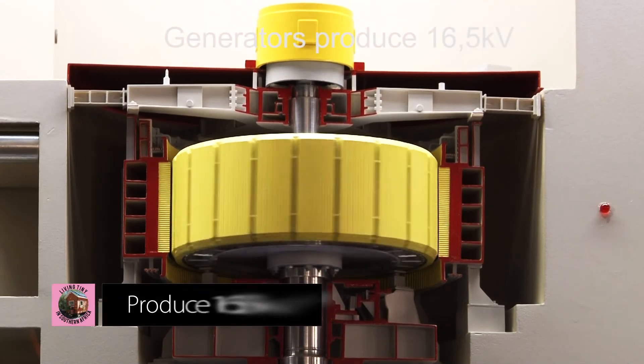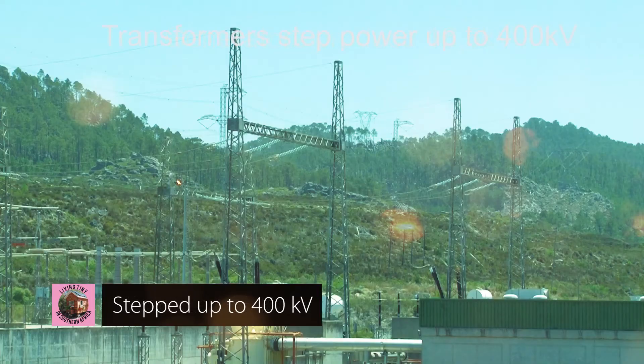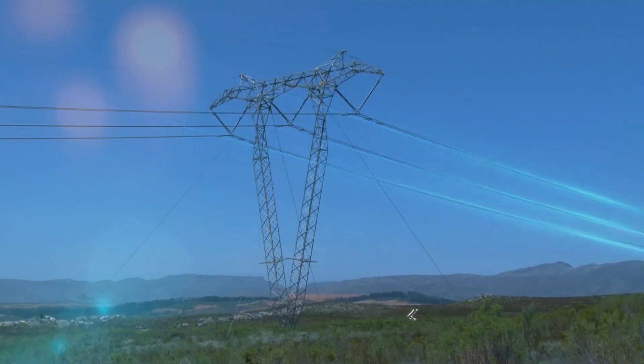The generator motors produce 16.5 kilovolts, which is then stepped up to 400 kilovolts by generator transformers installed in the high voltage yard just outside the station. Two 400 kilovolt lines connect into Eskom's national grid.